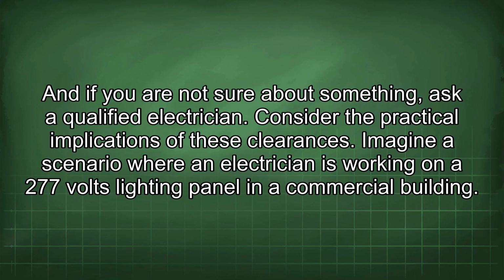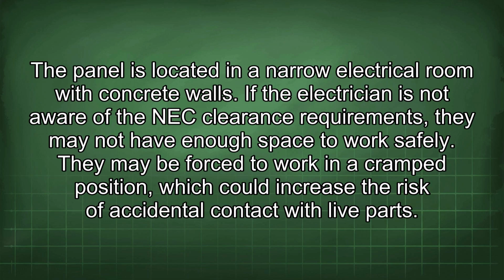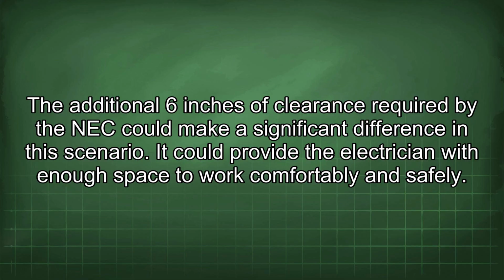Consider the practical implications of these clearances. Imagine a scenario where an electrician is working on a 277 volts lighting panel in a commercial building. The panel is located in a narrow electrical room with concrete walls. If the electrician is not aware of the NEC clearance requirements, they may not have enough space to work safely. They may be forced to work in a cramped position, which could increase the risk of accidental contact with live parts. The additional 6 inches of clearance required by the NEC could make a significant difference in this scenario. It could provide the electrician with enough space to work comfortably and safely.